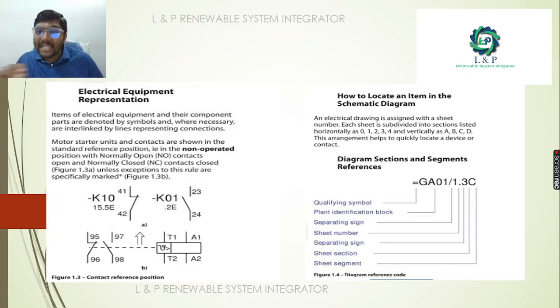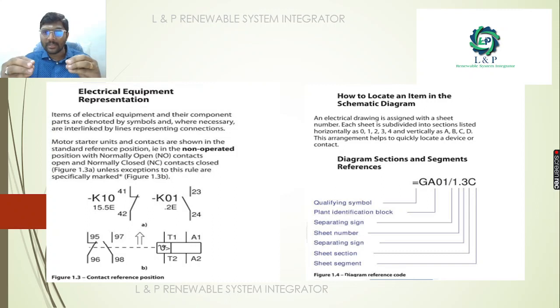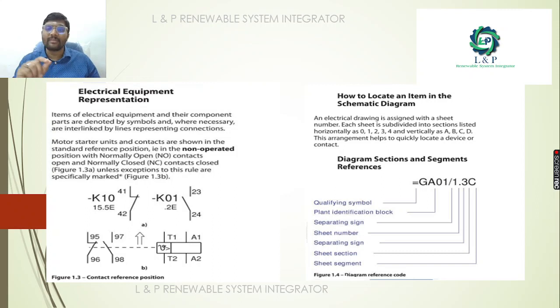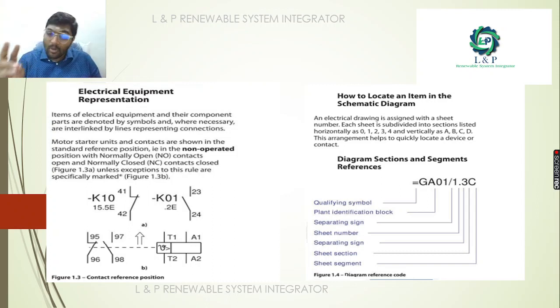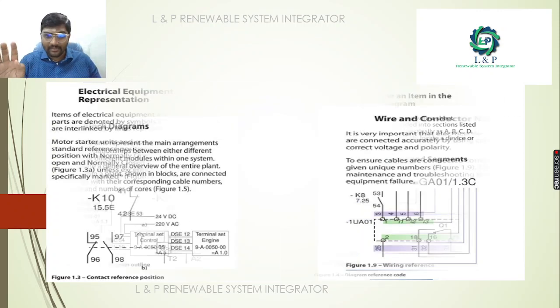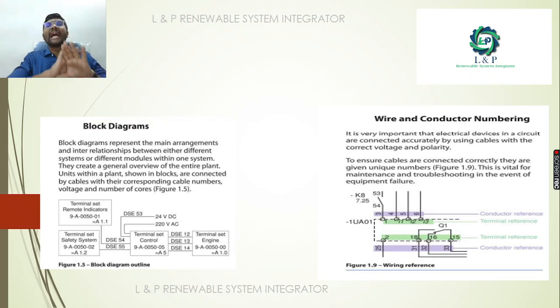Next is how to locate an item in the schematic diagram. In a drawing, we might have a sheet number, and each sheet number is subdivided into sections — represented horizontally from 0 to 1, or vertically as A, B, C, D, E. For a diagram section segment reference, we need: a qualifying symbol, plant identification block, a separating sign, sheet number, another separating sign, sheet section, and lastly sheet segment.